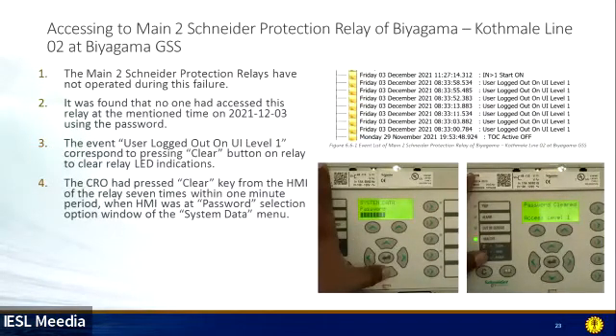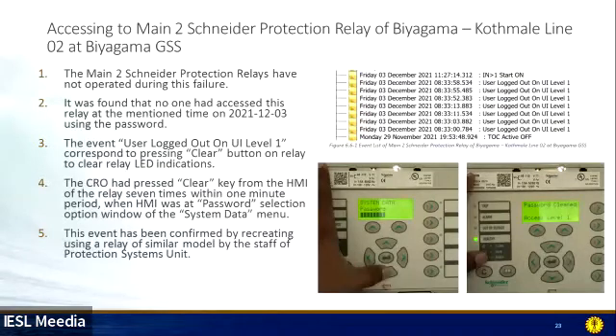The event user logout on user interface level 1 corresponds to pressing the clear button on the relay to clear relay LED indications. The CRO had pressed the clear key from the HMI of the relay 7 times within a 1 minute period when the HMI was at the password selection option window of the system data menu. That's the summarized information we received from the OEM. This event has been confirmed by recreating it using a relay of a similar model by the staff of the protection system. After obtaining the clarification from the OEM, our staff were also able to recreate this event and see that it actually happens like this.